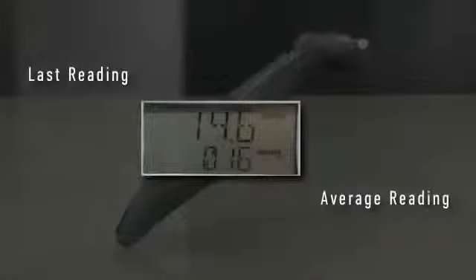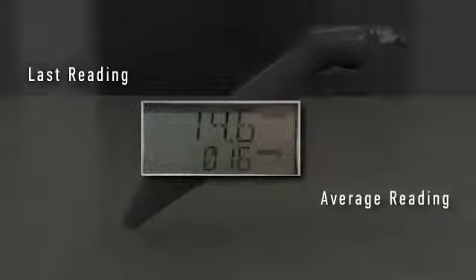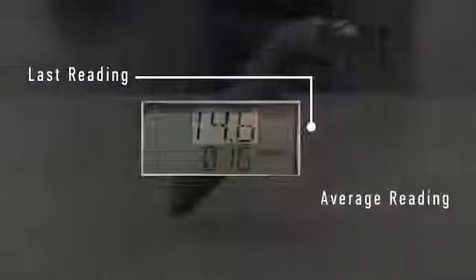The AccuPen has a proprietary algorithm which eliminates the need for a confidence factor. The AccuPen has the ability to store 9 IOP measurements. Once you have completed a measurement, you can simply press the Action button to take another measurement if necessary. The top number on your liquid crystal display will indicate the actual IOP measurement. The number below indicates the average measurement.